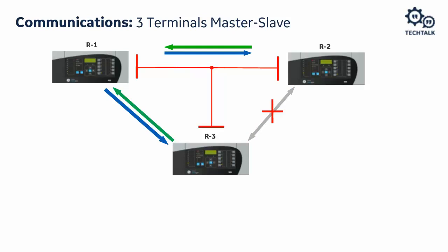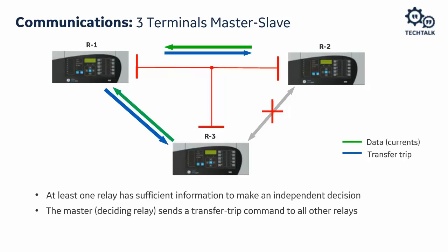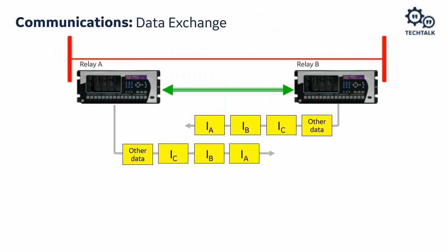In the three-terminal configuration, if one channel fails — say between relay three and relay two — those two relays still send data to relay one. Relay one still has all information needed to detect the fault, and the system reconfigures to master-slave mode. Relay one becomes master, makes the differential decision, and sends DTT to all other relays. The fault is cleared, so there is redundancy built in even in the three-terminal configuration.